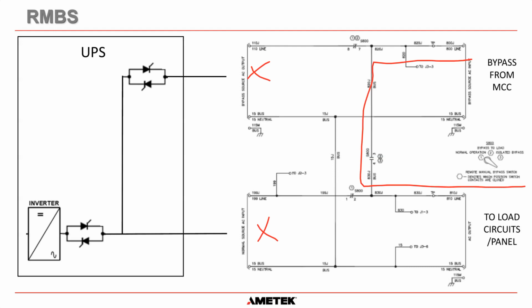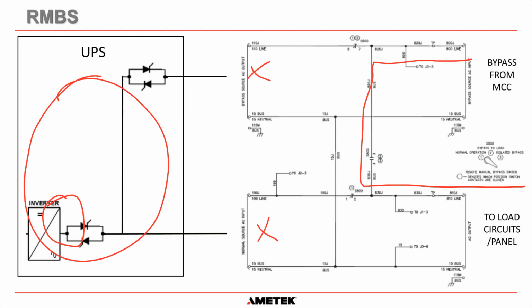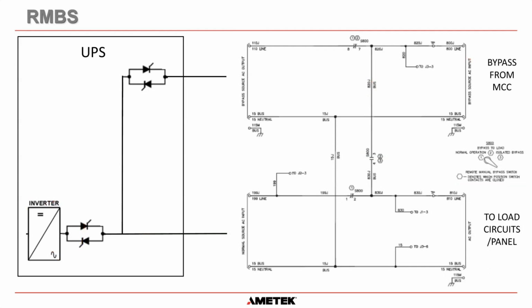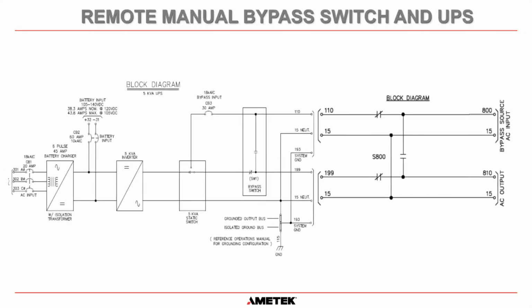So what we can do in this circumstance is we can go in, we can switch off the inverter, we can disconnect the batteries, we can switch off the AC input, and now we can make this whole UPS system volt-free so we can do in-depth maintenance, troubleshooting, repairs, and in truth, we can replace that UPS if absolutely necessary. Because here's a better drawing for you to see what's happening.